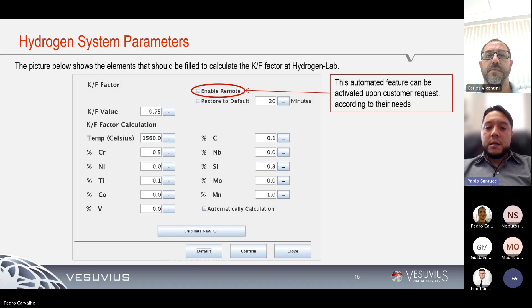So that helps the steelmaking process, once again, to find and determine a more accurate hydrogen value at the end of the measurement. And once we get this new feature set up between our equipment and customer level 2, all data is loaded automatically. So no more manual inputs will be needed afterwards.